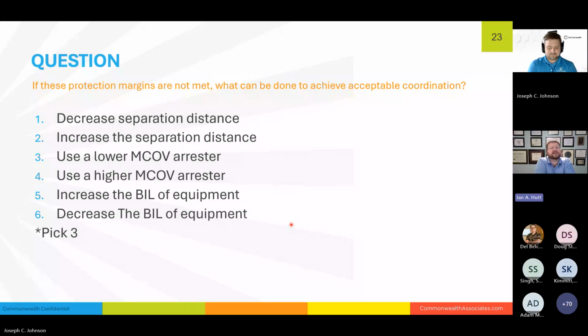Yep, here we go. So, question here. Talking about these protection margins, what mitigation steps do we have to improve our performance when we get into situations where performance is a concern? Maybe we're close to margins and we want to get more margin on those acceptable margins, or just beat them alone. So this is a pick 3 on this one. Pick the 3 that you think are going to make the difference. Do we decrease or increase the separation distance? Do we use a lower or higher MCOV arrestor? Or do we increase or decrease the BIL level of the equipment?